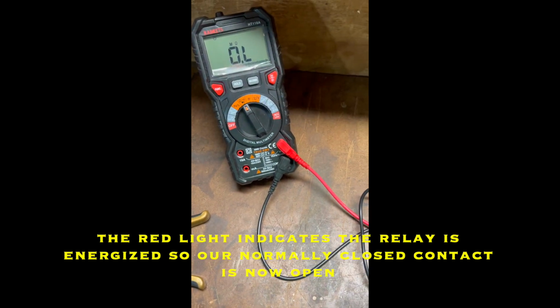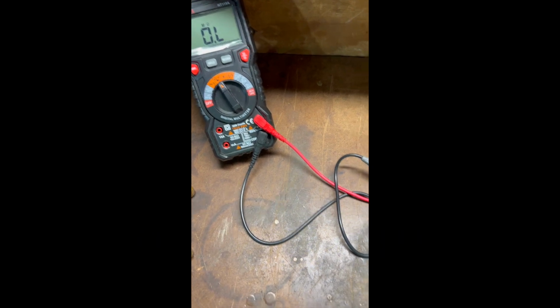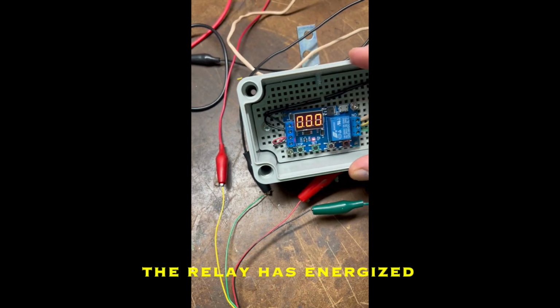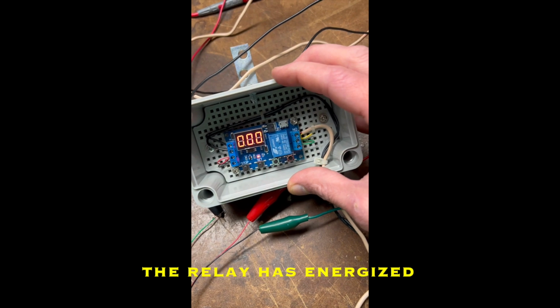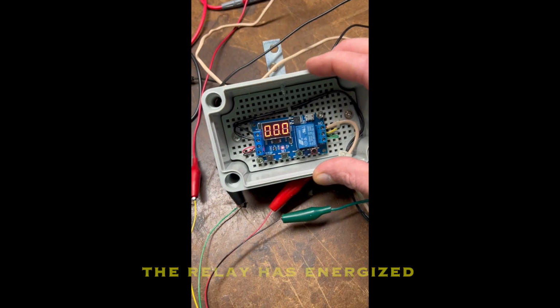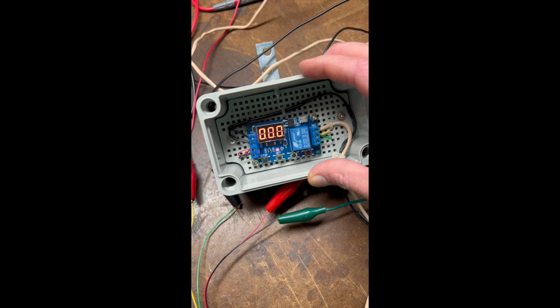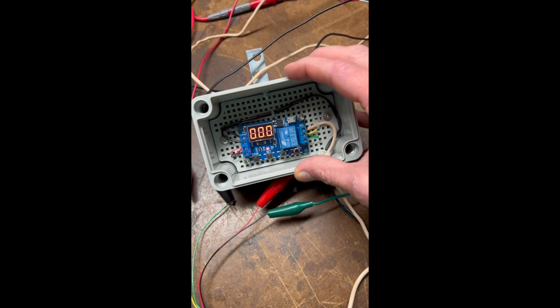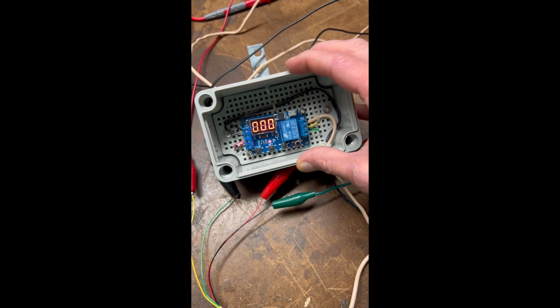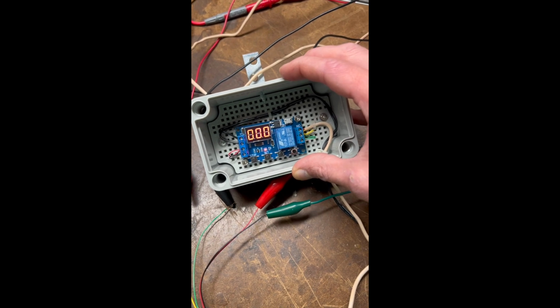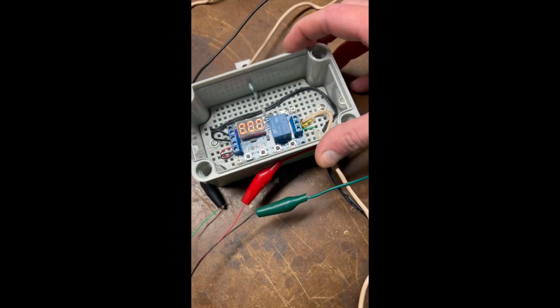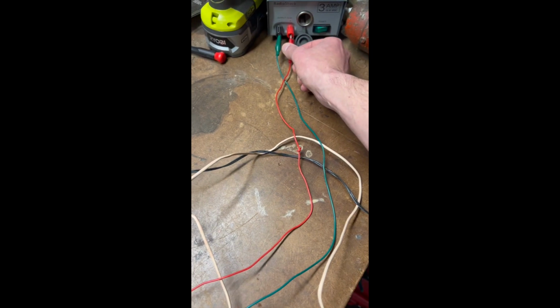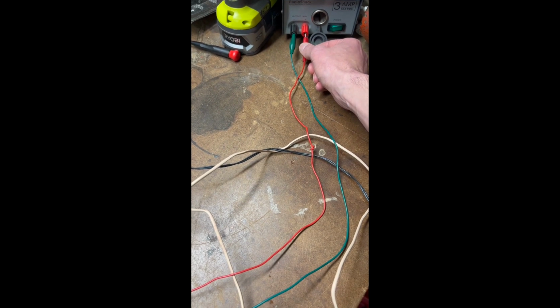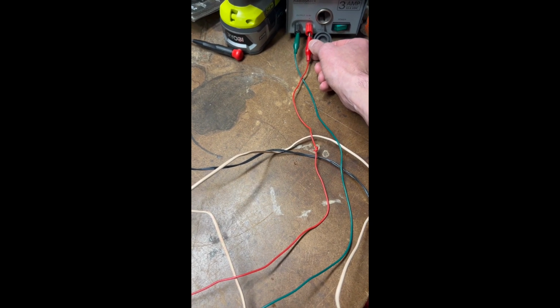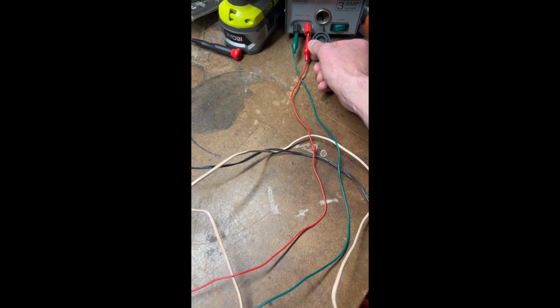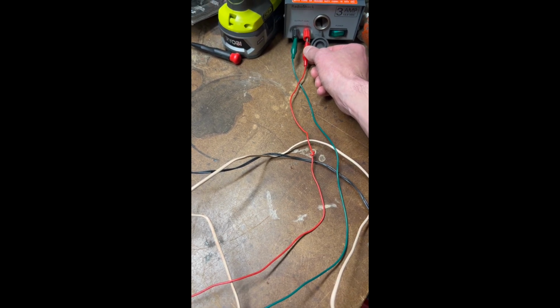Our ohm meter now is in an open position. The relay has opened up, or activated, and I'm using the normally closed contact, so therefore it is open. So this is a non-alarm condition as far as the water alarm is concerned. At this point, if I remove my trigger voltage, so this will be voltage that I'll be getting from the Liberty alarm panel that indicates when that circuit has lost power, and we'll go over that later.